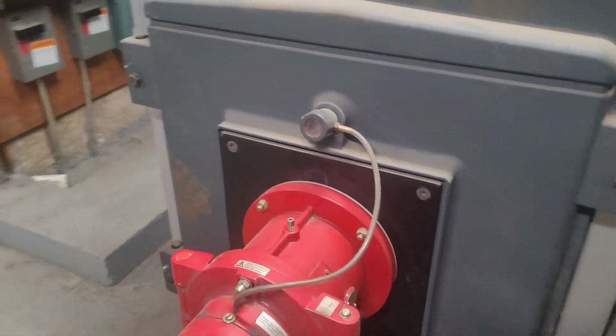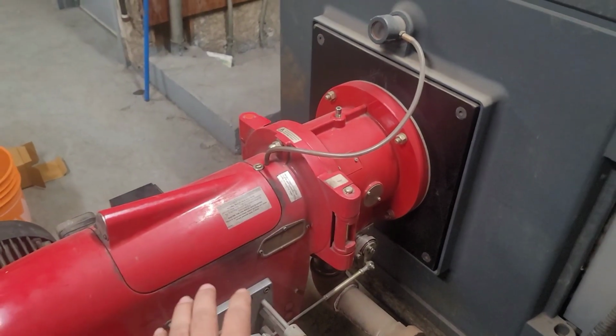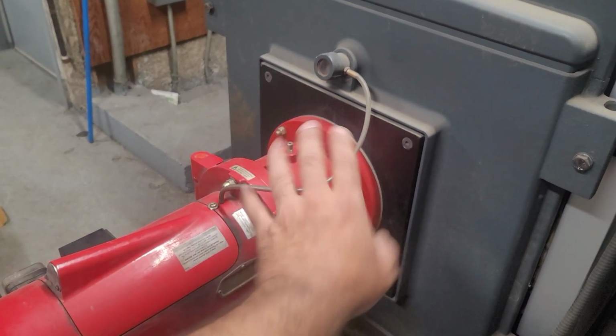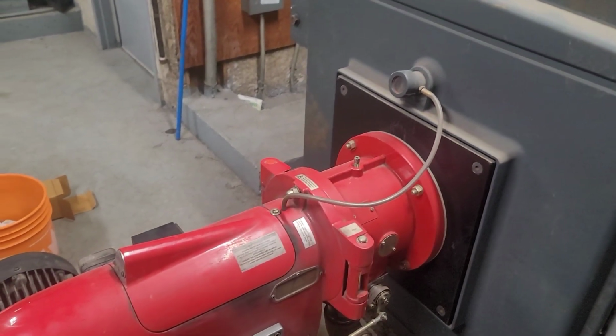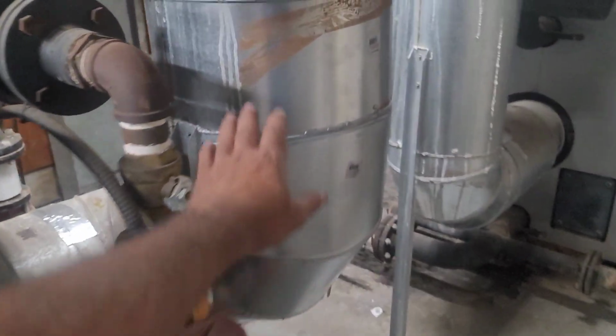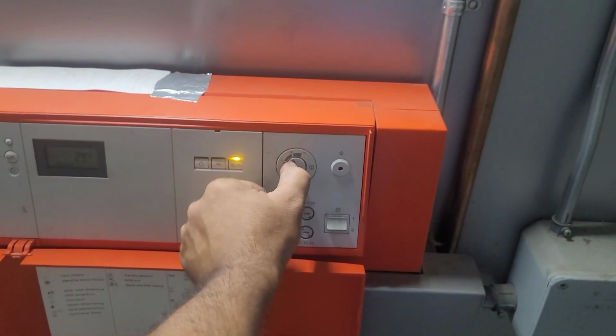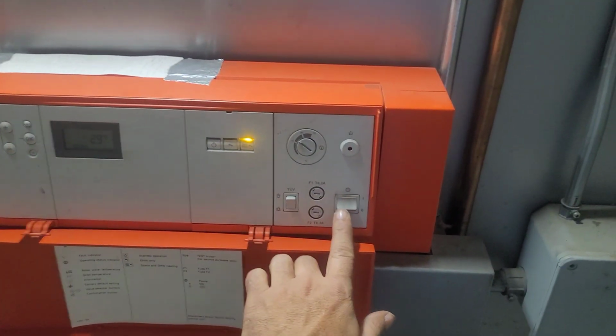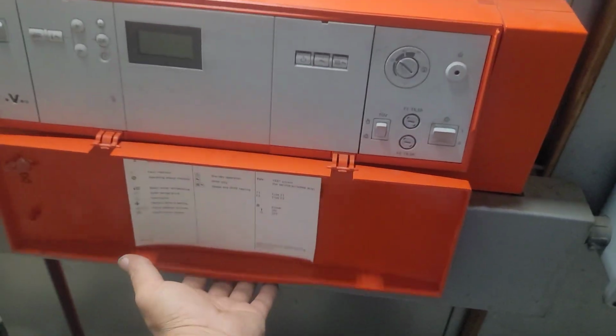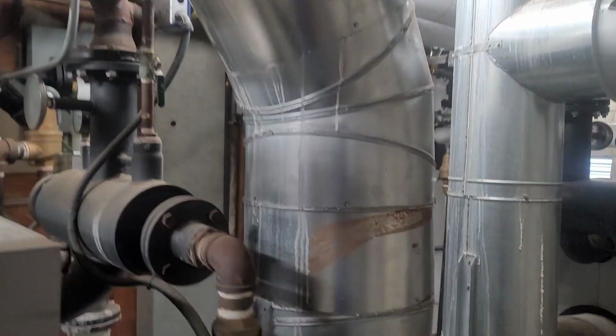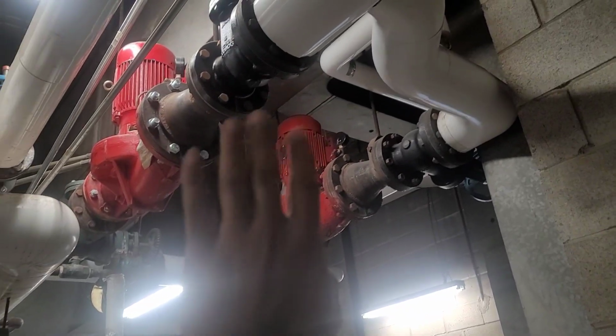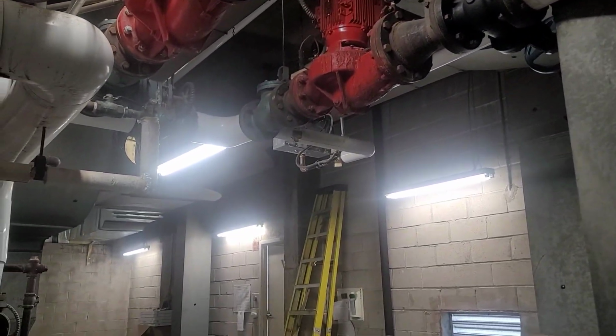Okay, so the boiler is running fine, and I just wanted to make sure the new burner, igniter and flame sensor are holding the flame. It's not going on ignition lockout or something. So it's running fine. That was just a test fire. So I will put the high limit to the low side, and I'm not touching the temperature, just turning it off, because I cannot run this continuously without turning on the main circulation pump, which are these two giant motors, which circulate the water throughout all the floors for heating.